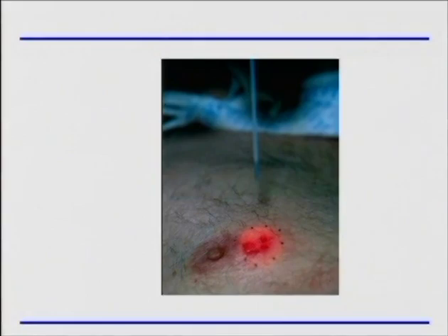This is a way that we treat lesions on the skin. If you're using a laser, then there's a little micro lens on the top which gives you quite a nice, smooth, slowly widening beam. It's not quite collimated, but it does allow you to alter the beam width just by pulling the fiber away a little bit. So in this case, we don't have a diffuser at the end of the fiber, so we have to use a different sort of technique.